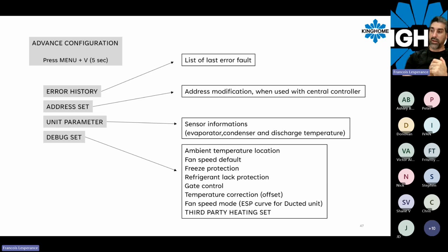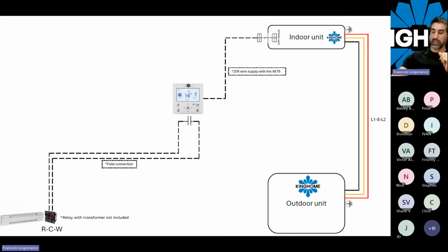The last part is the third-party heating set. This is what is unique to the Kinghome product. For example, if you have to do an installation, basically you will run your 4 wires, counting the ground, to the indoor head, so L1, L2, S, and your ground. You have your COM manual connection here, so you will hook the 25-foot long wire to the controller hanging on the wall. Then from that controller, we have a relay. There's logic behind this relay to be able to control another relay with a transformer.